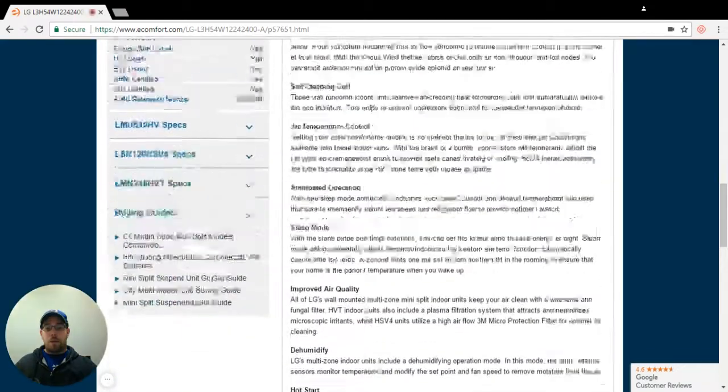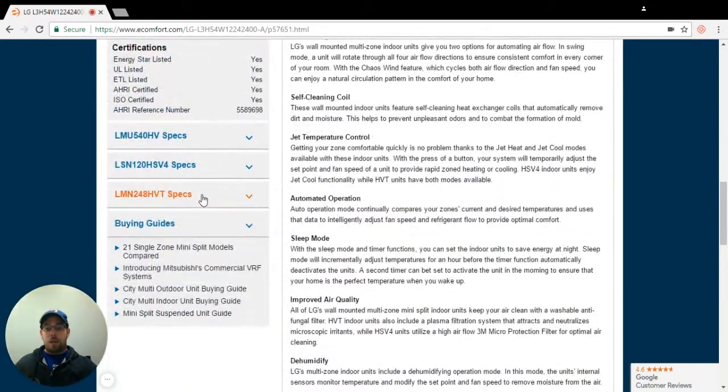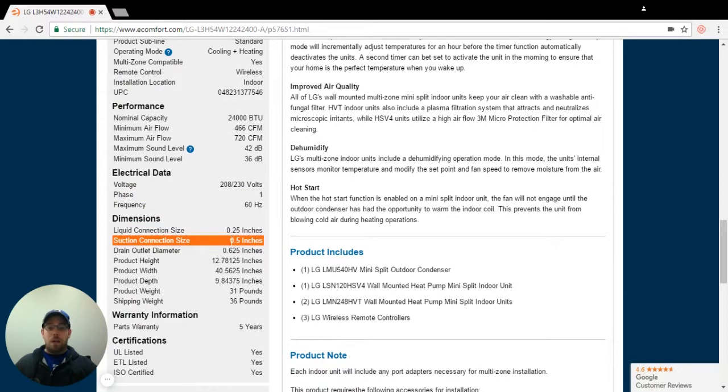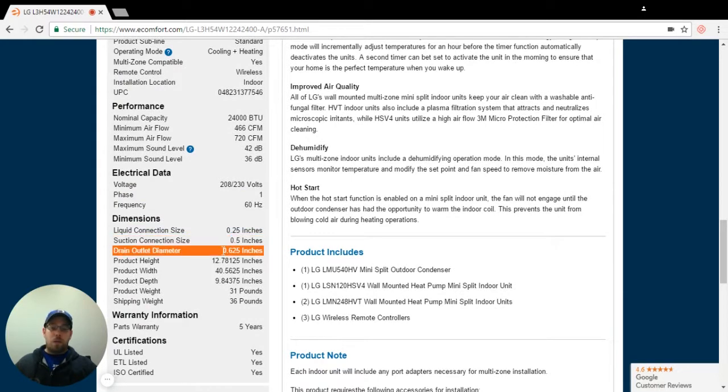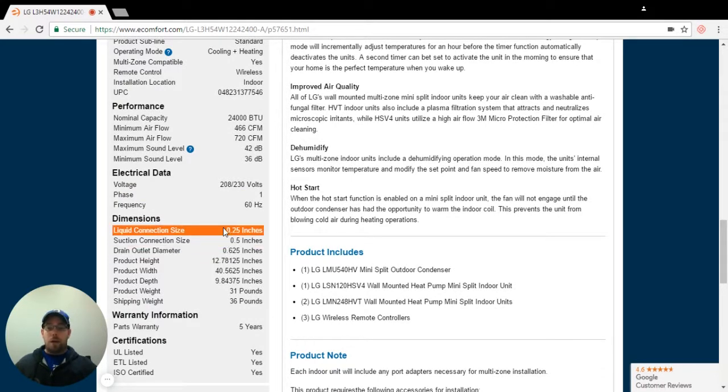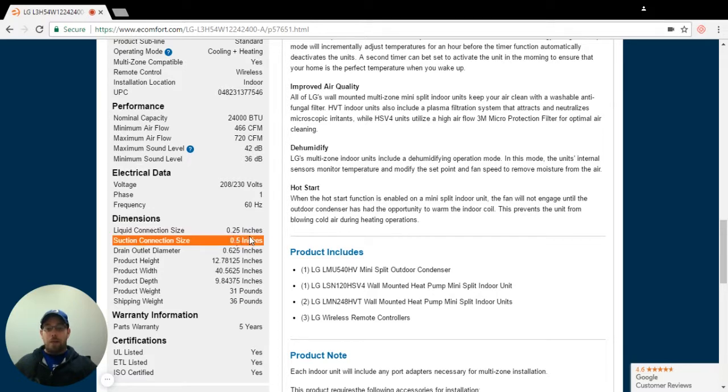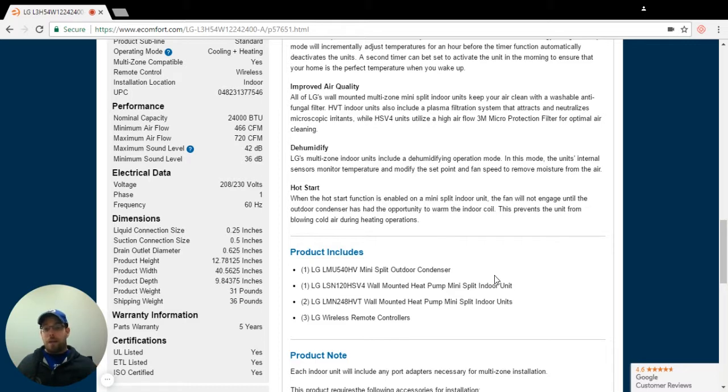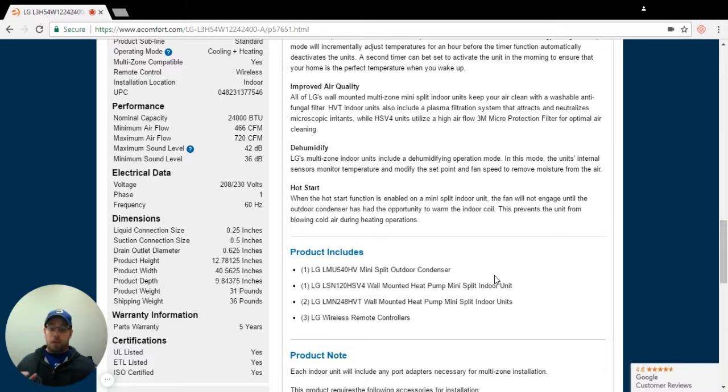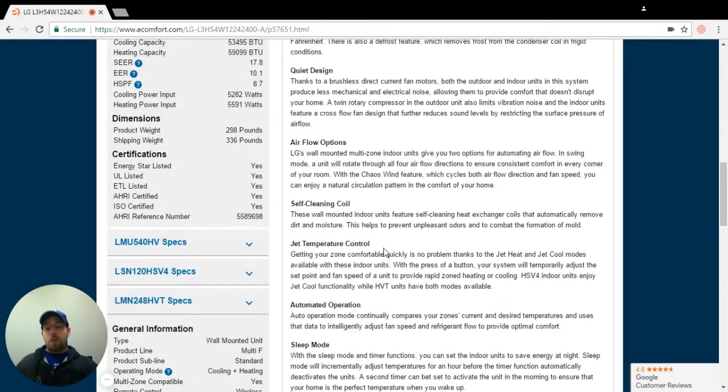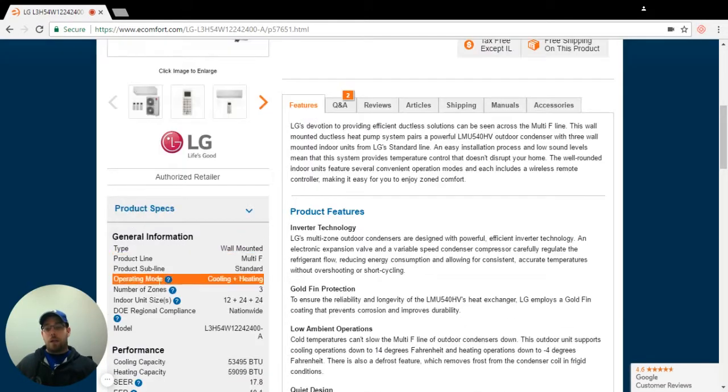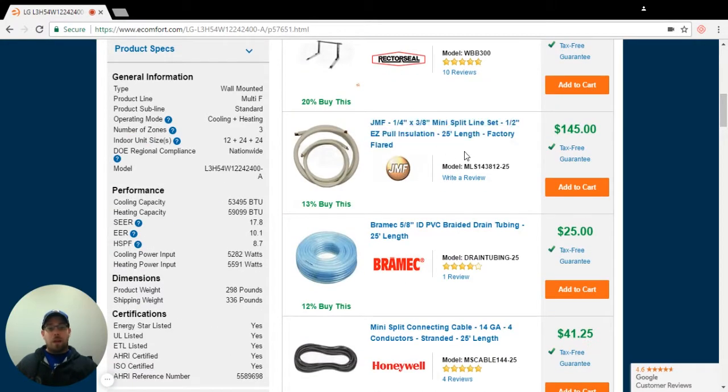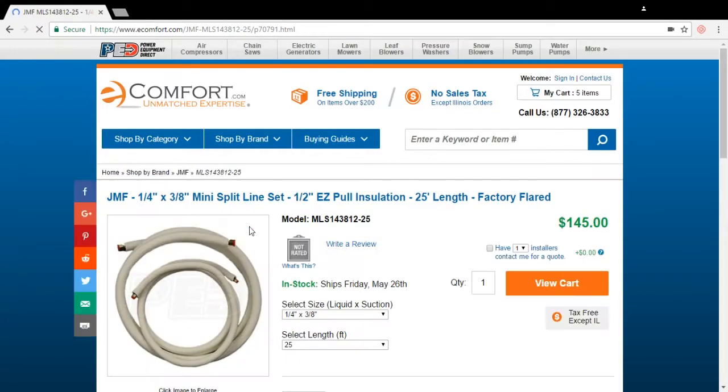Now what I'm going to do is go down. I'm going to see what size line set my 24 is going to be. Now, each one of those is going to be about 25 feet away. So this is going to need to be quarter by half of the line set on this. Now, once again, I've stated before that if you look at the single zone version of this, it might say three eighths by half or three eighths by five eighths. It will change from single zone system to multi-zone system, depending on the brand. Always make sure you check either the installation manual, or check the head units that we have listed under our specs here.